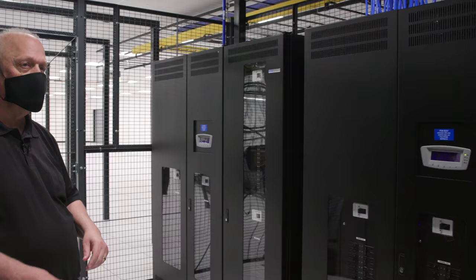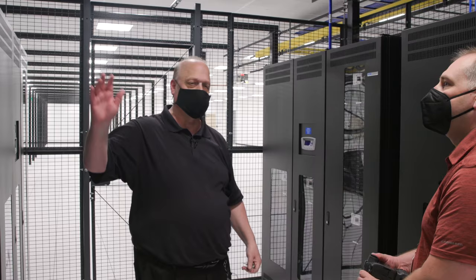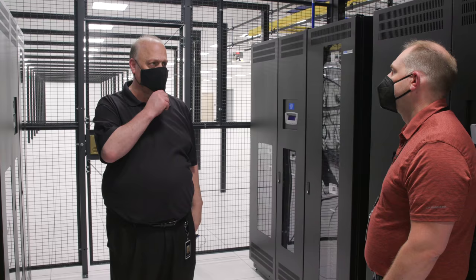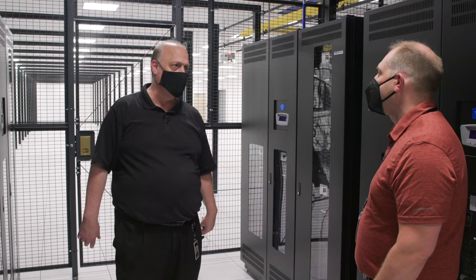We're upstairs at the power distribution block of the second-floor data room. The substation downstairs steps it from 12,470 volts to 480 volts coming into the facility. One of those substations feeds this multi-distribution point — all 480 volt — and each breaker comes out to feed a PDU, which is how we get power to the various cabs and cages. We don't get many requests for 120 volt anymore unless it's in quarter cabs; the norm is 208 volt. This facility is designed at 200 watts per square foot and can go up to 500. Normal cabs are about 5kW, with some 25kW and 43kW cabs available.